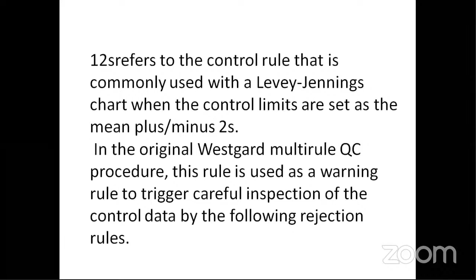This is a random error which is unpredictable and can happen at any time, and there are several causes for this. To summarize, this gives you a warning that you need to check your system and you must repeat the same level of the control, and if your second run or your rerun is within 2 standard deviations, you can continue with the process. If not, what is the indication? 2 times 2 standard deviations. As you can see the red points below minus 2s.